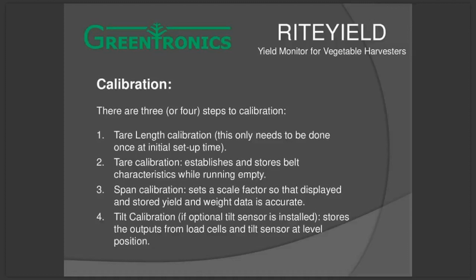The next step is span calibration. So now you go and run a known weight over the conveyor. You can use a block of wood if you like, and run it over so that you accumulate maybe 200 or 300 pounds. Then you enter that number in the span calibration menu, and that sets a multiplier inside the console so that it knows that when it sees 300 pounds, that's 300 pounds. I hope that makes sense. Ideally, you do that with a truckload. But we can get within the ballpark by using a small weight.